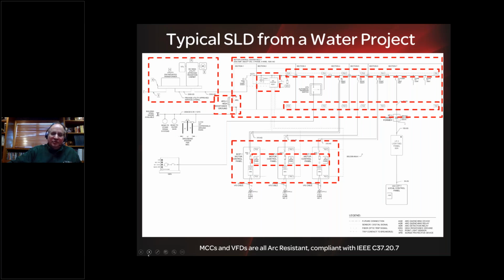So before you go into any piece of equipment without arc rated PPE on, because in the case of arc quenchers, as if you've seen the previous arc quencher presentation, we always eliminate the NFPA 70E requirement for arc rated PPE. Specifically, that means we always reduce the incident energy below 1.2 calories per centimeter squared at the IEEE 1584 working distance, which for these low voltage assets would be 18 inches.